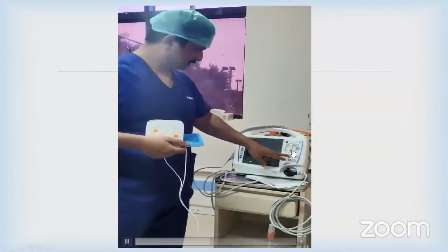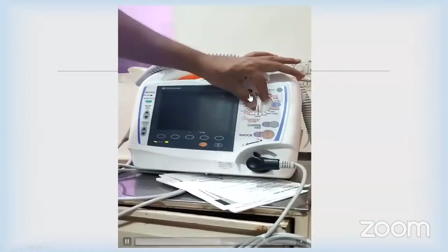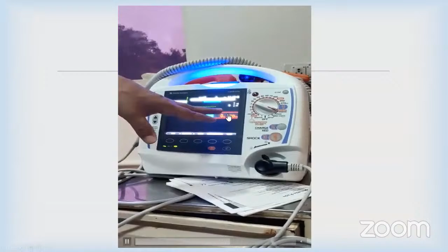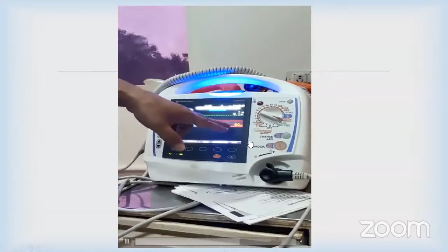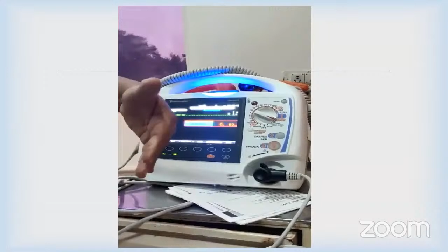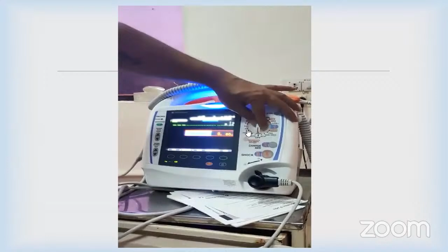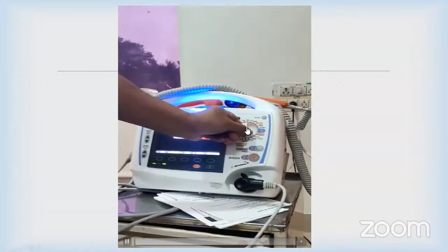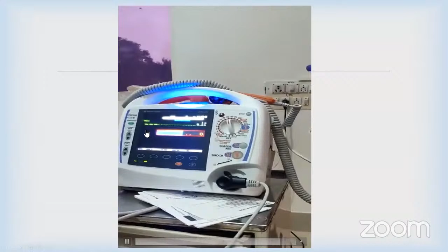In this defibrillator, you have a pacemaker mode as well as a cardioverter or defibrillator mode. You put it in pacemaker mode, it will go into asynchronous mode, AOO or VOO, DOO, whatever it is, and it will give you the transcutaneous pacing. When your PPM is not working, it is disrupted or has some problem, then you can go back to the transcutaneous pacing. Also, if the patient is on an ICD and you have disrupted the anti-tachycardia function, then you can do cardioversion as well as defibrillation depending upon the patient's condition with these transcutaneous pads. So that is the importance of it.